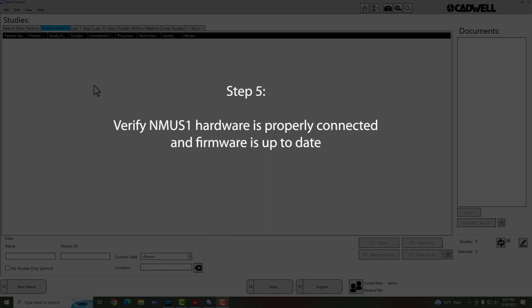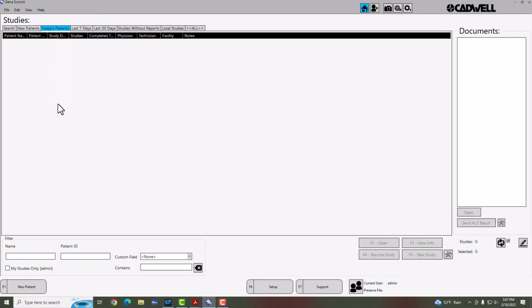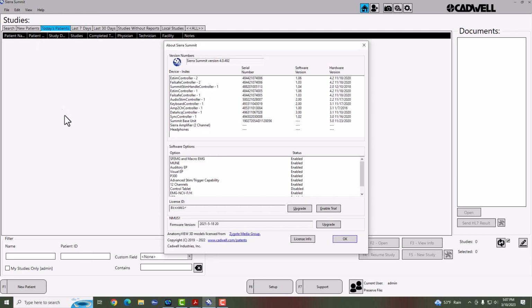Now go back to the Sierra Summit software and go to Help and About to ensure the device is connected and firmware is up to date. Where it says NMUS1 firmware version, it should say 2021-5-1820. If the date is older than this, you need to upgrade the firmware. If there's no date and it says hardware not connected, you've done one of the previous steps incorrectly.